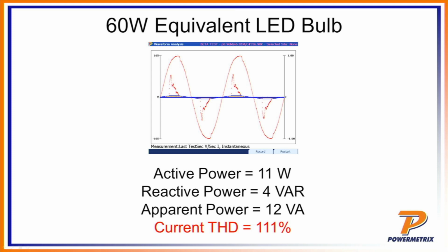The big loss, however, comes in harmonic energy. We have a current THD of 111%. And so what that means is there is more energy being dissipated as harmonic energy than fundamental energy. And once again, that's most likely going to be burned up as heat.